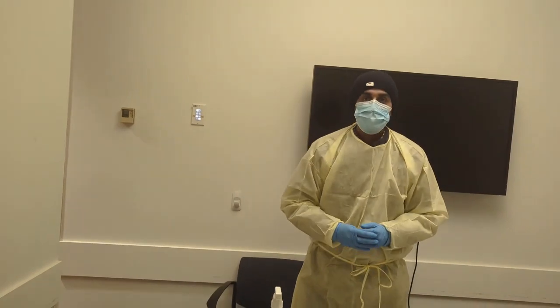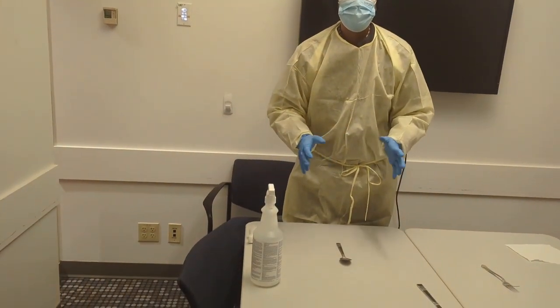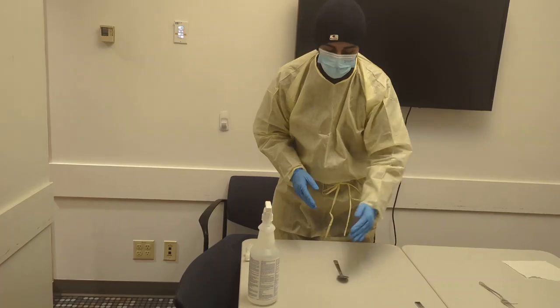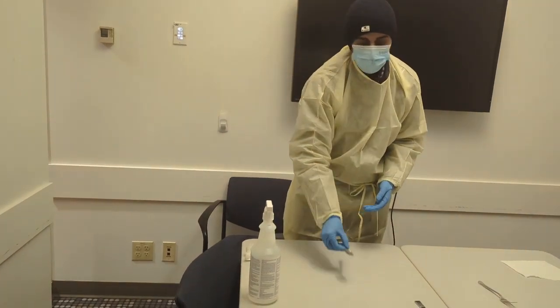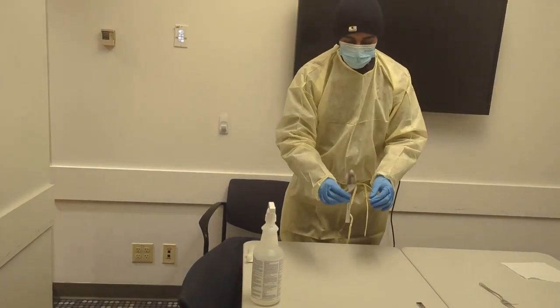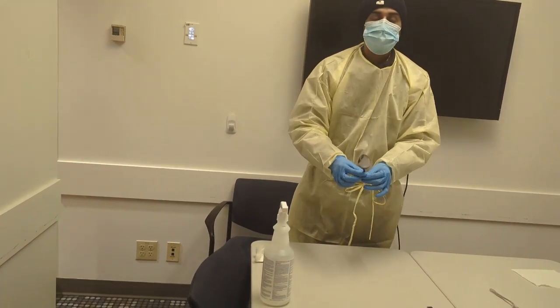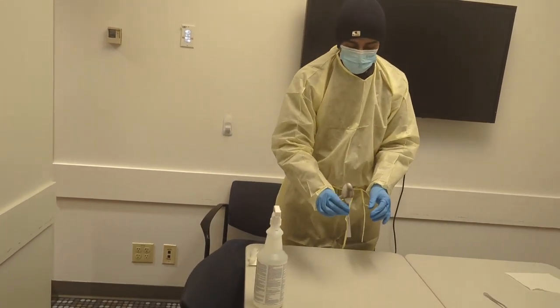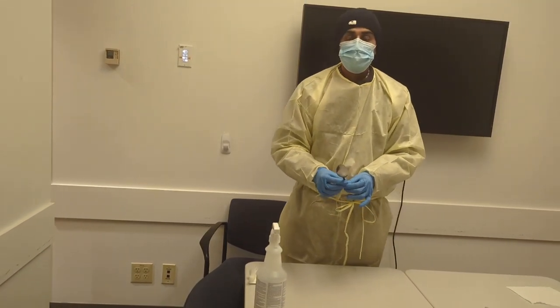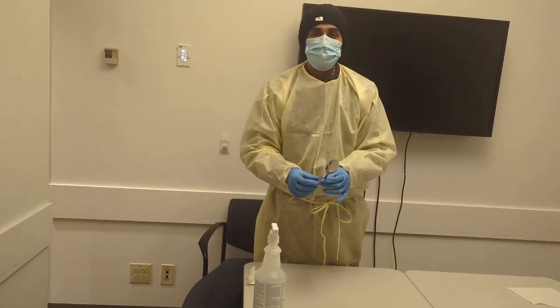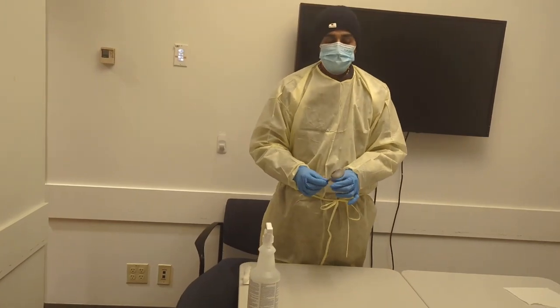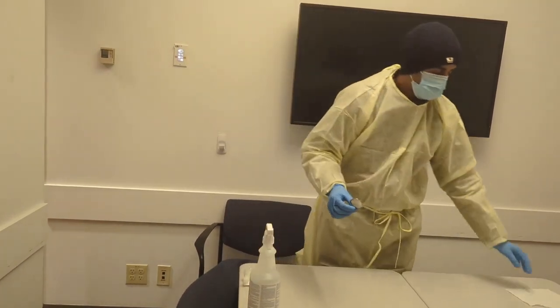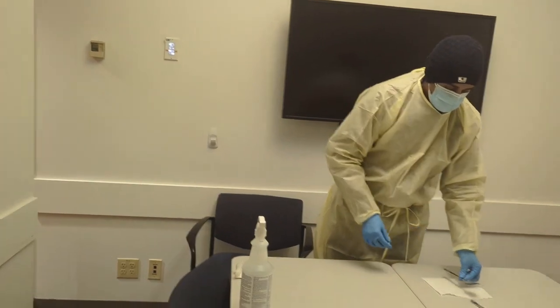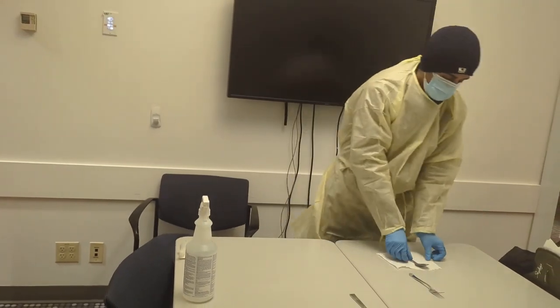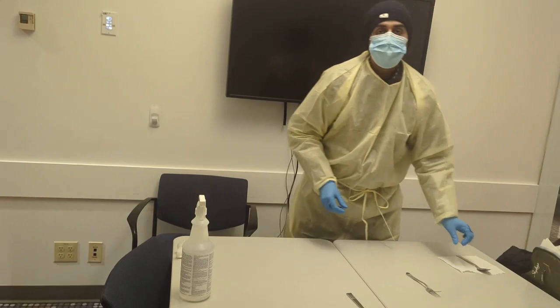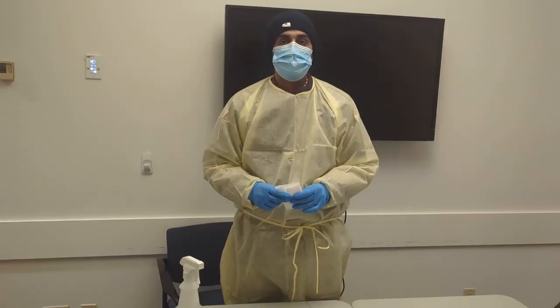Now the disinfection time period has elapsed, and we are going to remove the lid and take out our endoscope. If there is any excess disinfectant present, we are going to rinse it off, and then take some sterile water and rinse it with the sterile water. This is how we are going to later place it over a dry towel in a sterile area, and this is how we complete the disinfection.